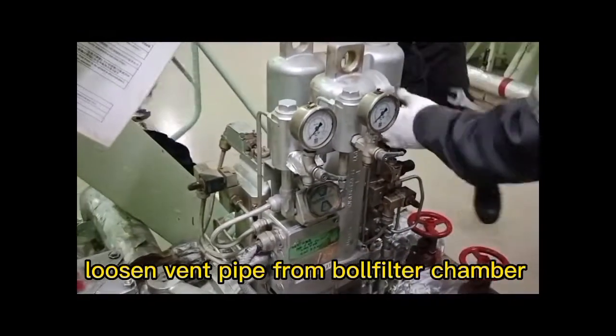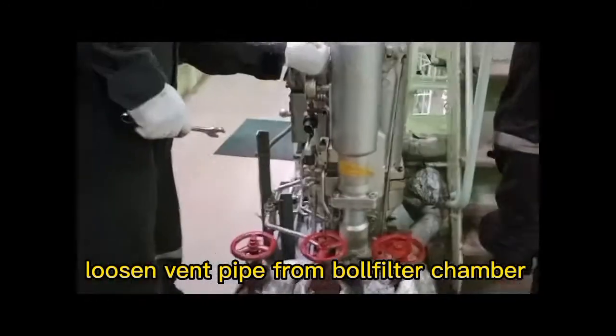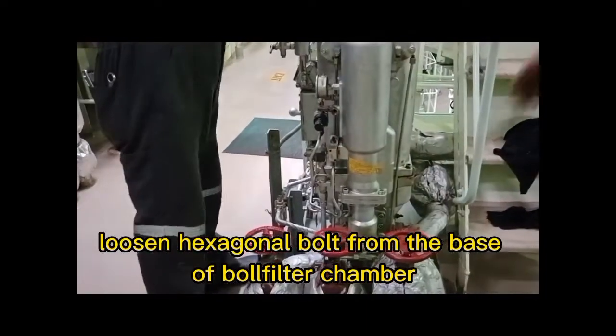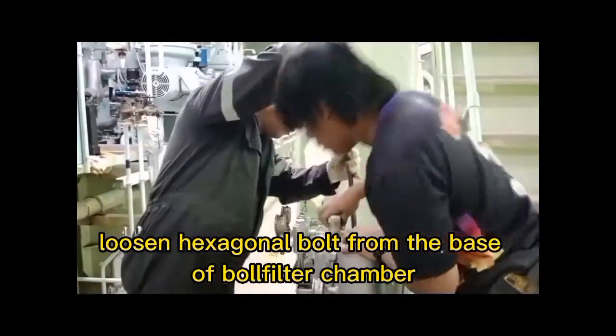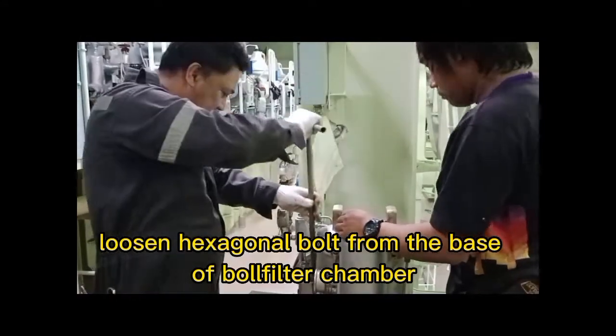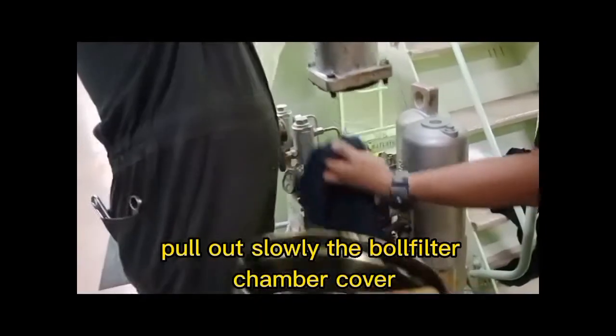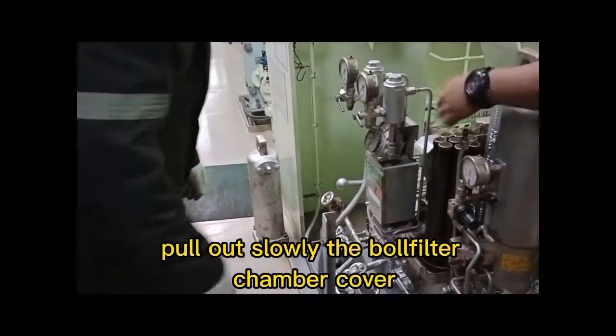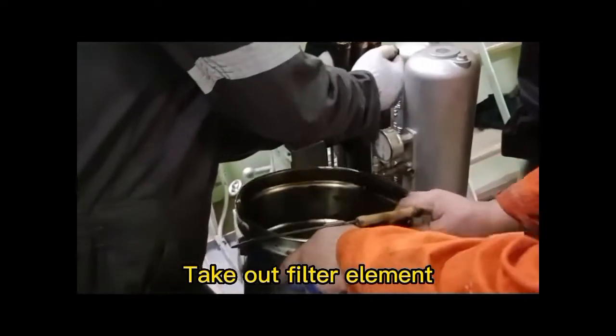Loosen the vent pipe from the ball filter chamber. Loosen the hexagonal bolt from the base of the ball filter chamber. Then pull out slowly the ball filter chamber cover and take out the filter element.